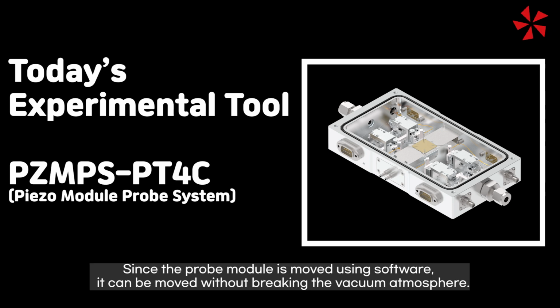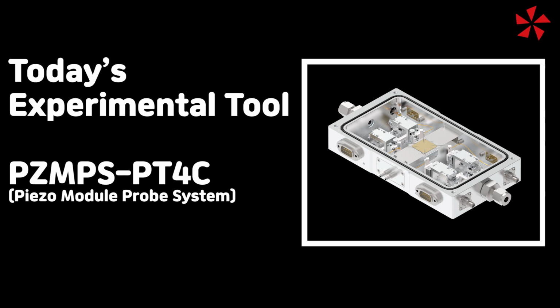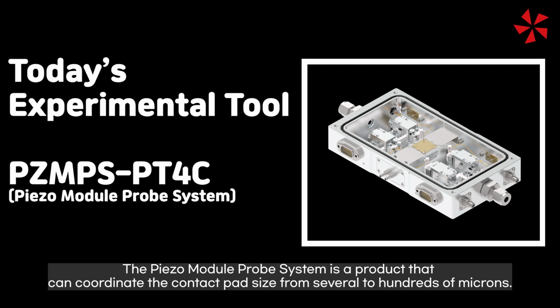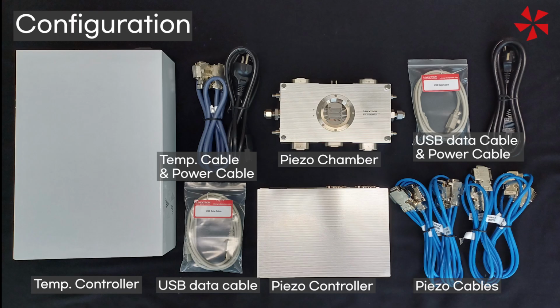Since the probe module is moved using software, it can be moved without breaking the vacuum atmosphere. The Piezo Module Probe system is a product that can coordinate the contact pad size from several to hundreds of microns. The components of the Piezo Probe Module chamber are: first, Piezo Module chamber; second, a Piezo Module controller; third, a temperature controller; fourth, a connection cable.